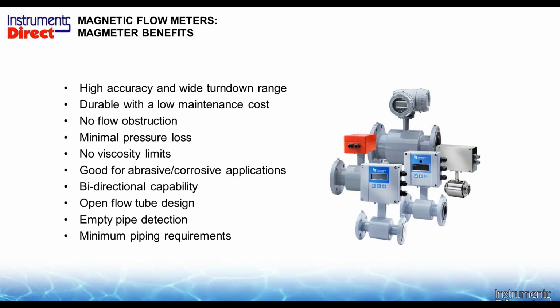Well, they are bidirectional because they can measure the going in and the going out. Most of them, as I said, are open flow tube design. And this particular brand we're going to look at today actually has empty pipe detection, which would be very helpful. And piled on top of that, we still have some really neat perks: most mag meters require a little less than the traditional flow meters for monitoring straight run of pipe applications.